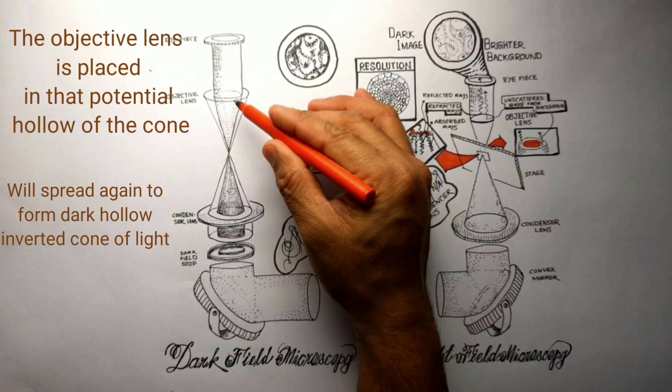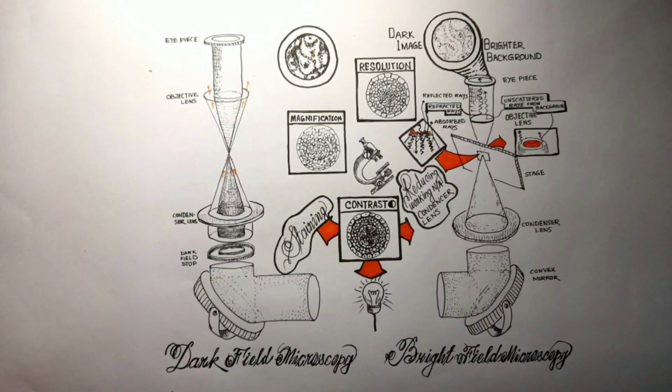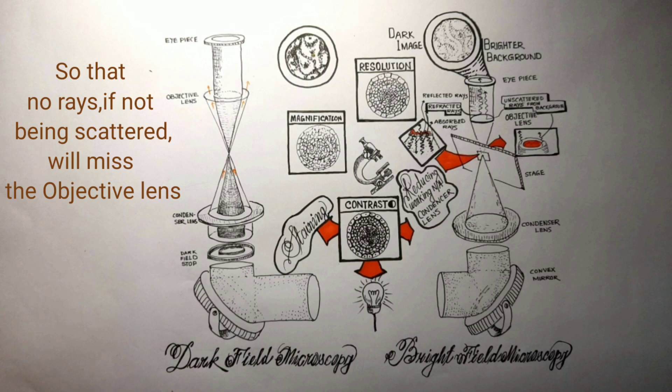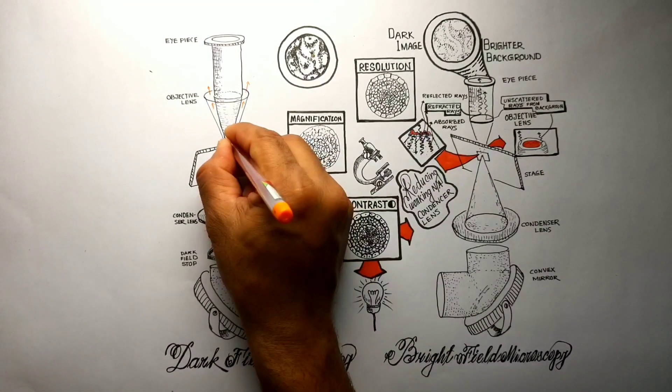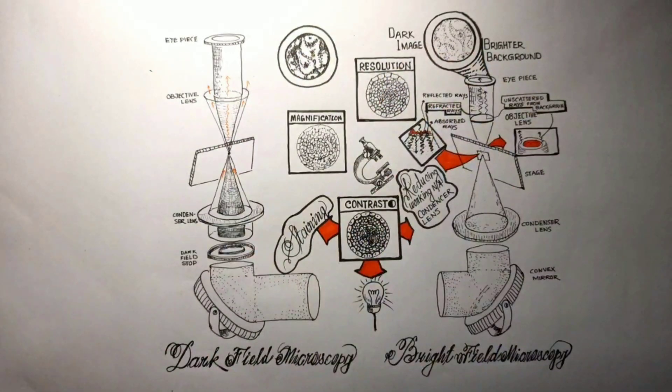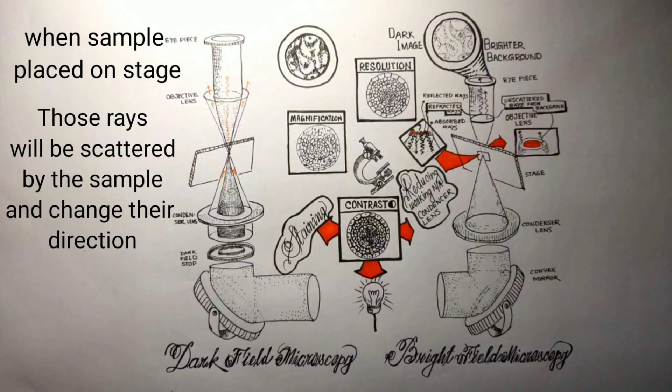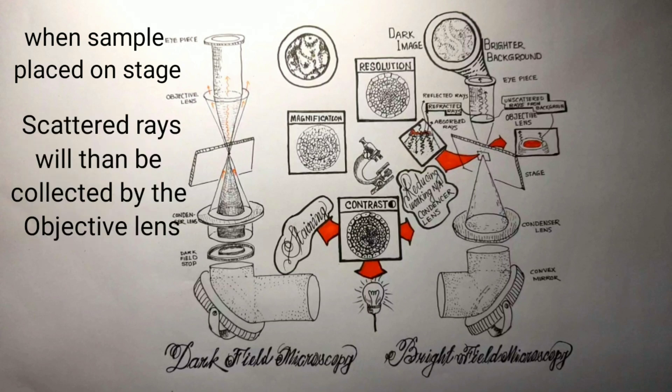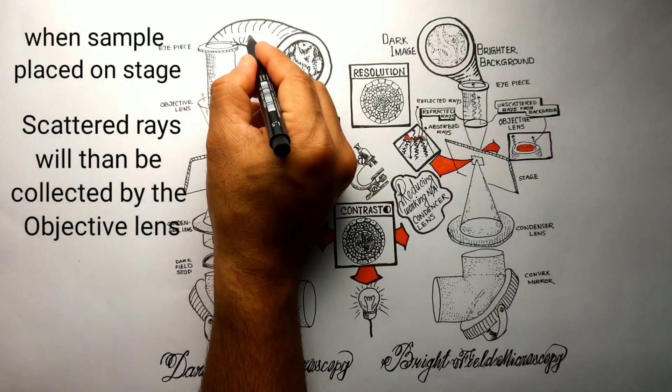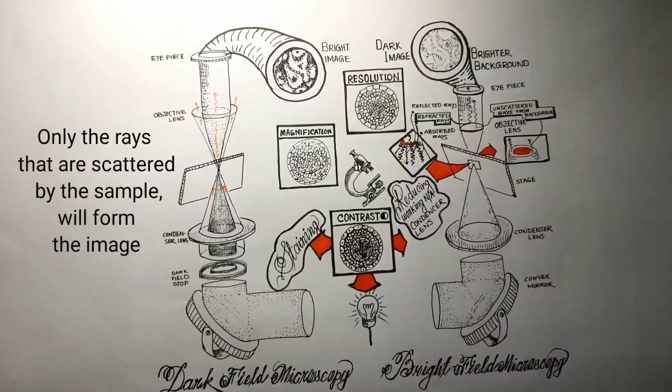In dark field technology, the objective sits in the dark hollow of the cone. As light propagates through and past, it will miss the objective lens, and no rays will enter. With no sample on the stage, the entire field appears black. When a sample is placed on the stage, the light strikes the sample at its sides and is scattered by it. These refracted and scattered rays from the sample are captured by the objective lens and used to form a bright image of the sample.